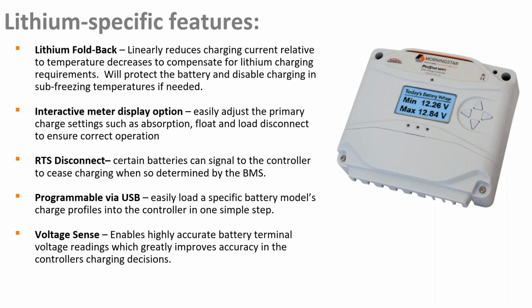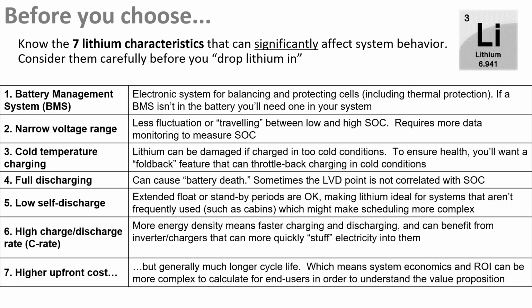However, being able to utilize that remote connection point, you can instruct the controller to turn off and disable charging, which is a valuable feature to prevent any sudden internal disconnects by the battery management system. In addition, you'll have really accurate voltage sense capabilities found on a lot of our controllers: a pair of terminal inputs where you can attach the voltage sense leads directly on the battery terminals, so you're compensating for voltage drop over a certain wiring distance. Again, that improves the accuracy and the regulation of the charge controller. So those are all things you would want to make use of in a lithium battery system.